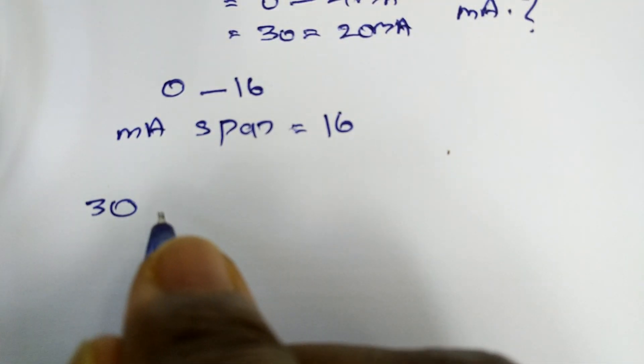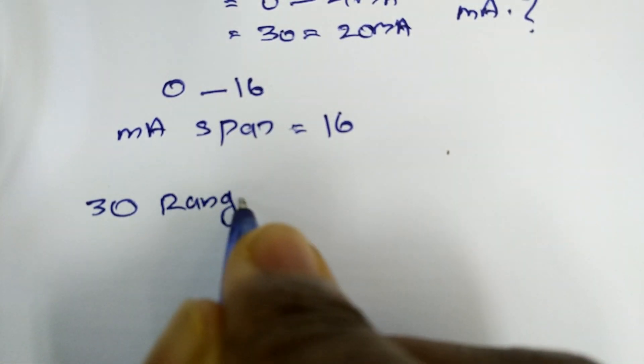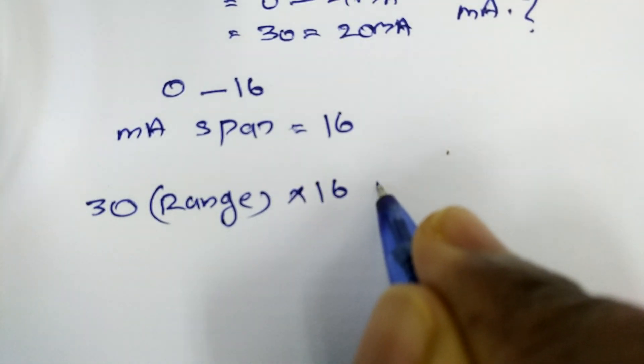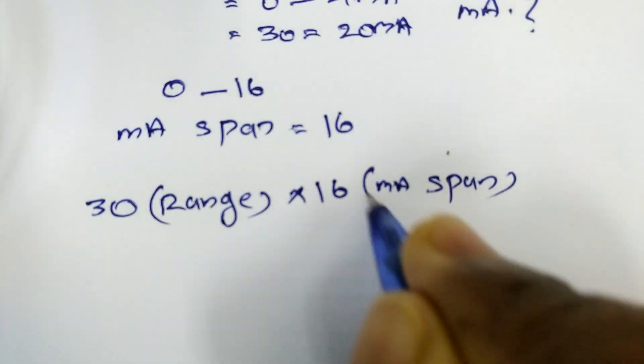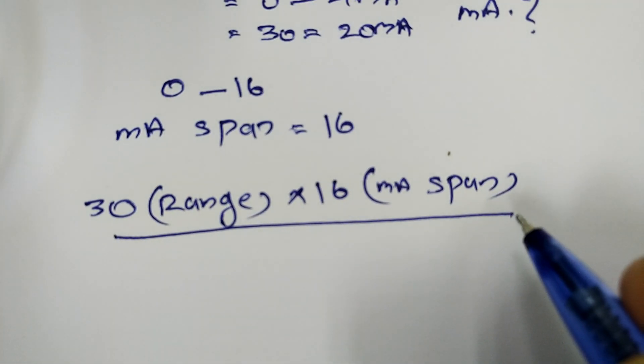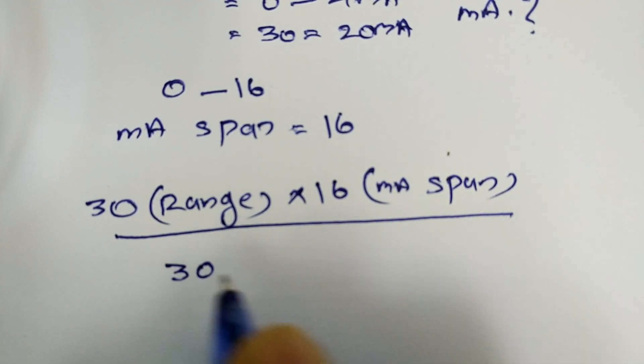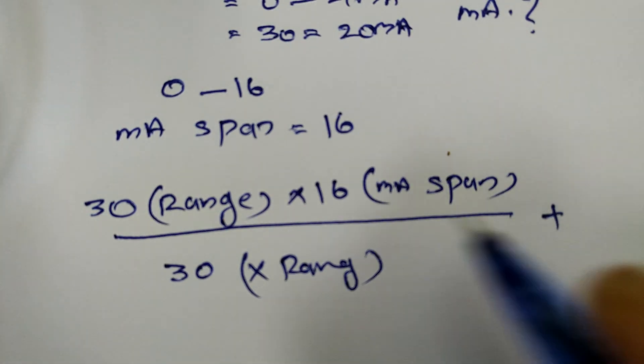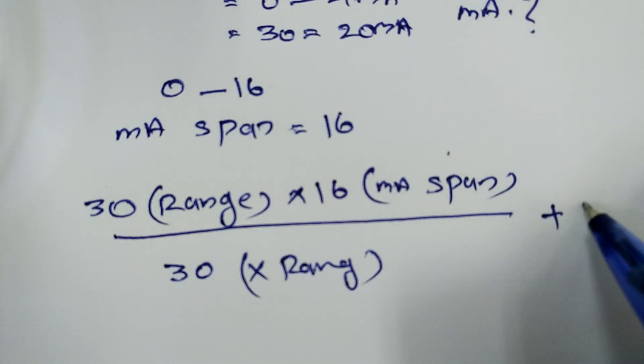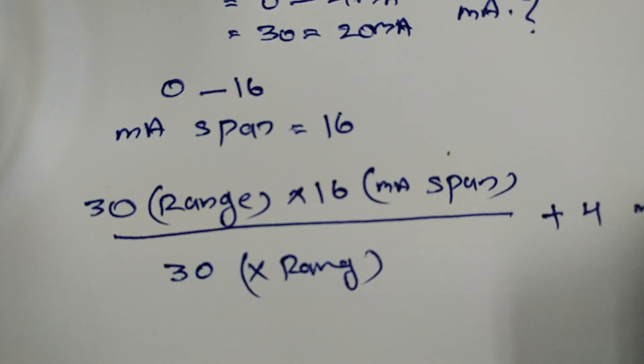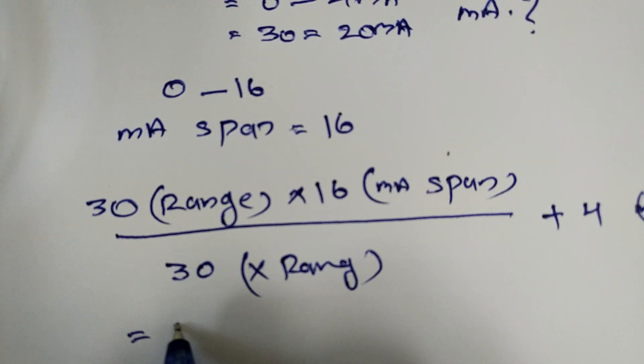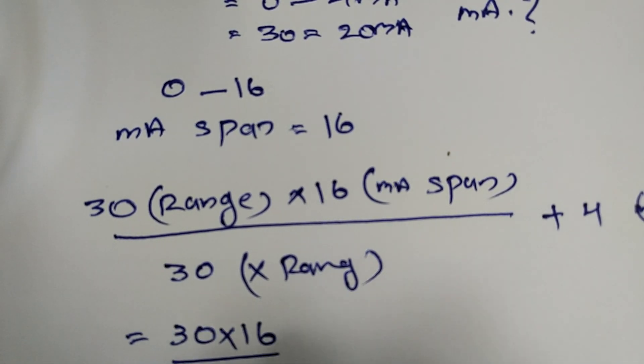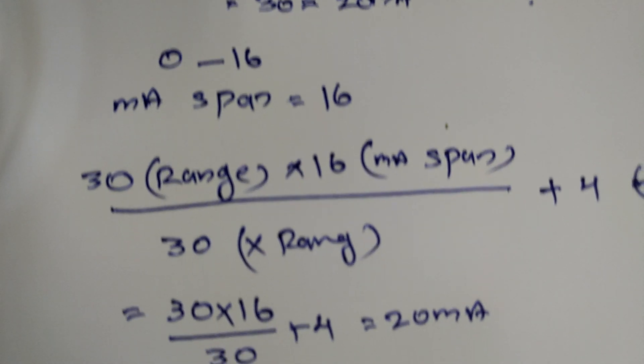For a range of 30, we add 4 mA. The equation is: 30 multiplied by 16, divided by 30, plus 4. This is equal to 20 mA. That is our equation.